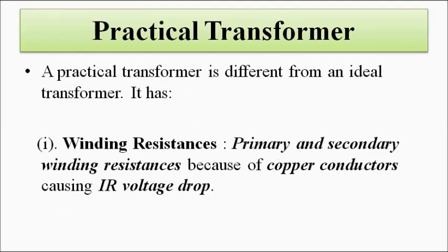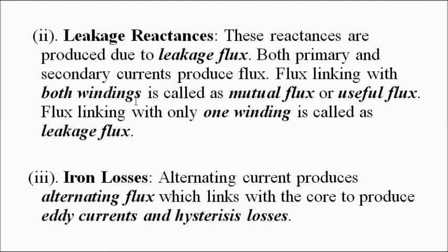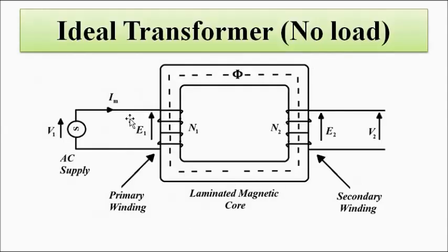In a practical transformer, both the primary and secondary windings have resistance values associated with them. The primary and secondary windings can be visualized as a simple RL circuit — they have some amount of resistance and inductance. In an ideal transformer it is only inductance with no resistance, but in a practical transformer it is an RL combination. The leakage reactances are produced because of the leakage flux.